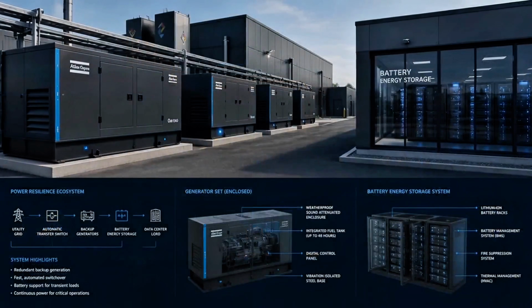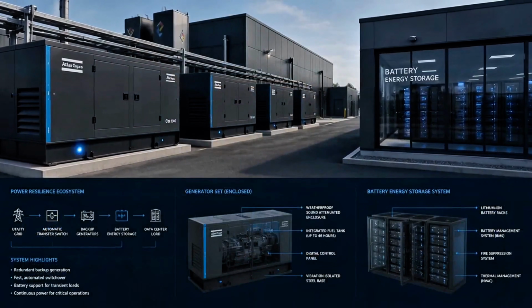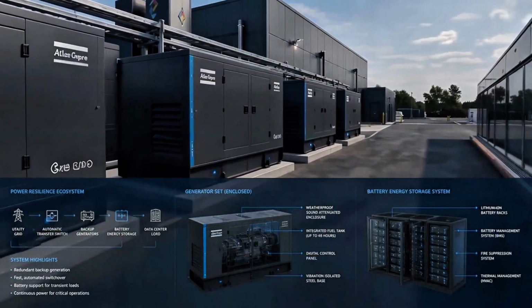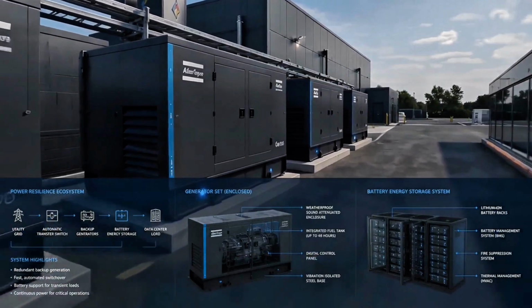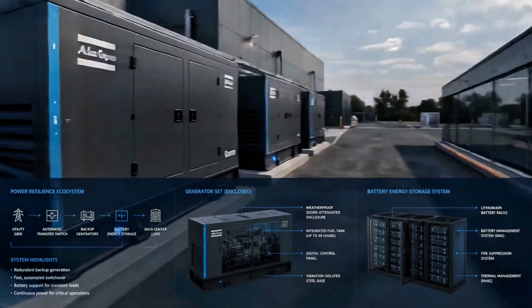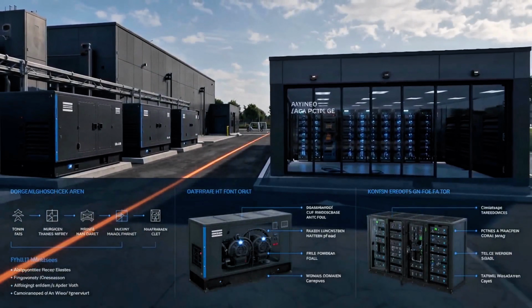If the outage continues, backup generators or other on-site power systems take over. Batteries can support short transitions, while generators can operate much longer. Redundant fuel, controls, cooling, and electrical paths are all designed around one goal: continuous operation.